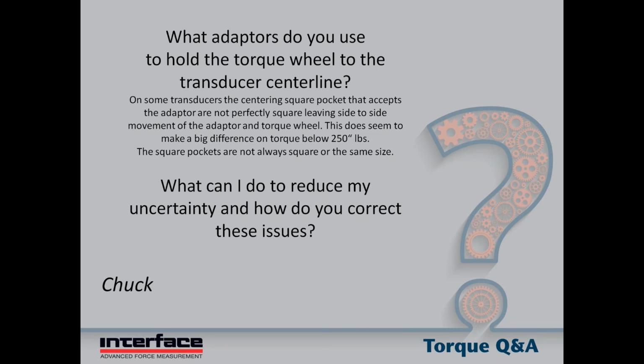Yeah, square drive torque sensors in general are notoriously known for poor fit. Basically, it's virtually a necessity when you're going to be changing out tool sockets and other tooling that's going to interact with the square drive. It's an accepted compromise that must be made when using a square drive sensor. I don't really know how there's any way for a production tool environment to utilize a square drive with any higher degree of tolerance than what's already there.